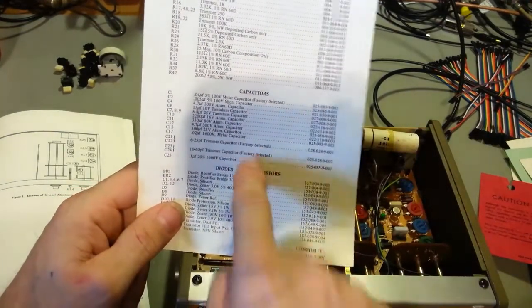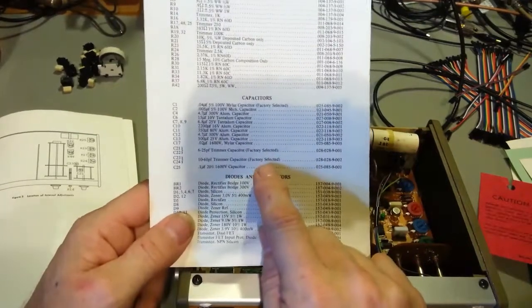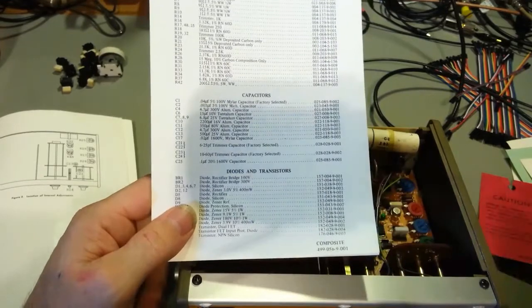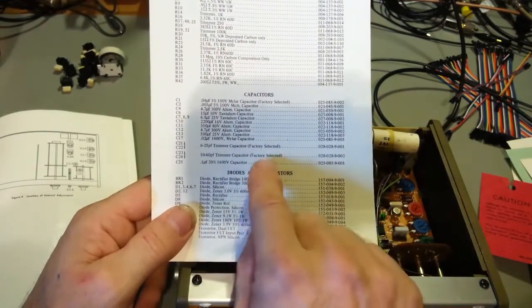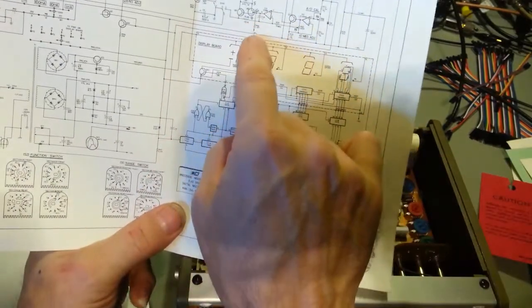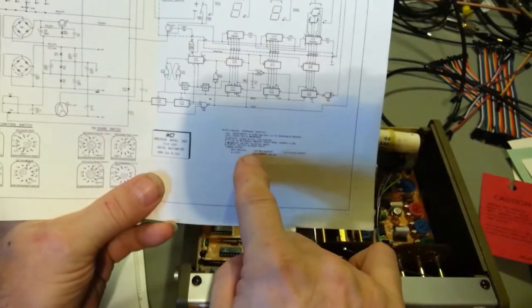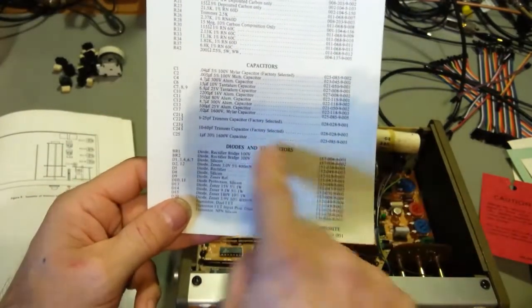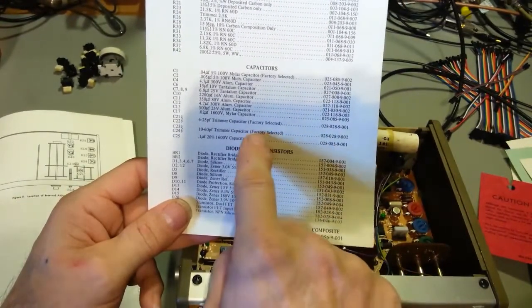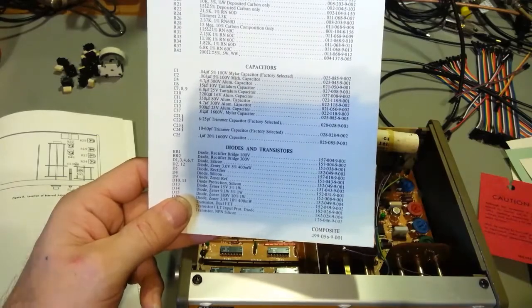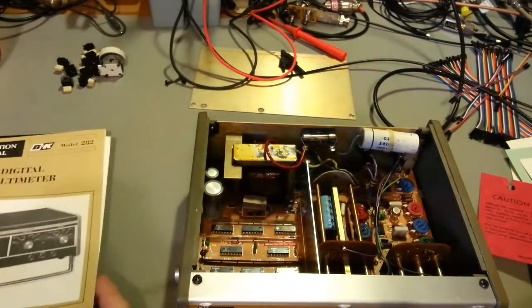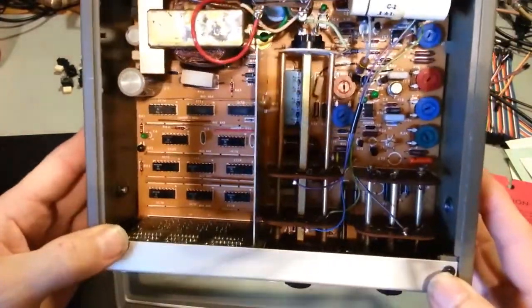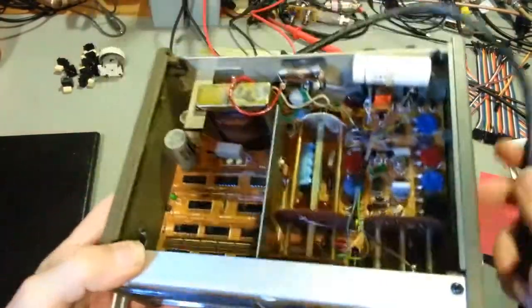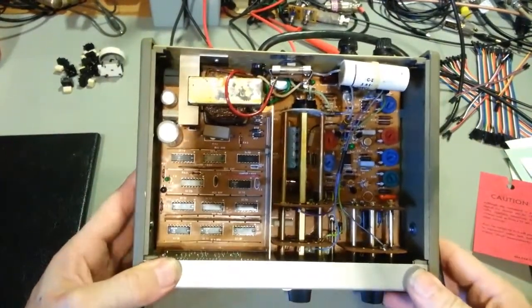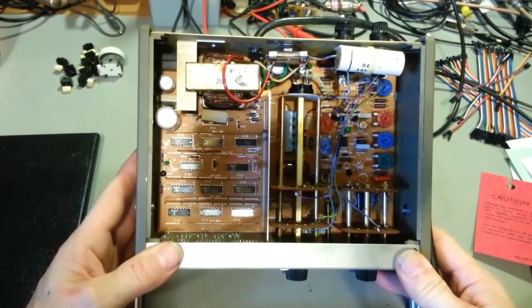So yeah, factory selected. And you'll see that even in radios and television sometimes. Older CB radios, now we're talking vacuum tube days or very early solid state. But a lot of times when you look at a schematic, you'll see a little asterisk by a part like a resistor or a capacitor, and when you look down in the legend, it'll say something like factory selected or selected at time of alignment. So yeah, it may just not need them. So we'll have to see if I'm going to have to change any capacitance to bring this thing into calibration. But like I say, at least the DC voltage seems to be within, actually a little bit less than 0.1 of accuracy. So, but there you go.